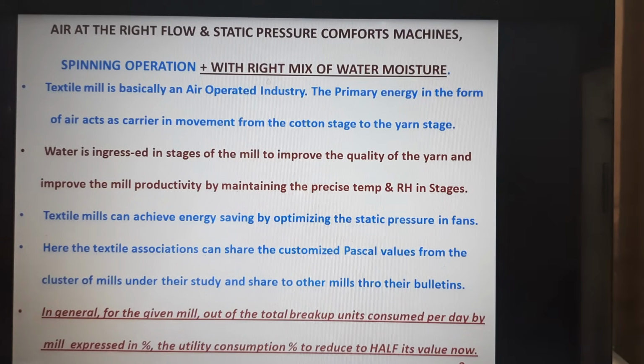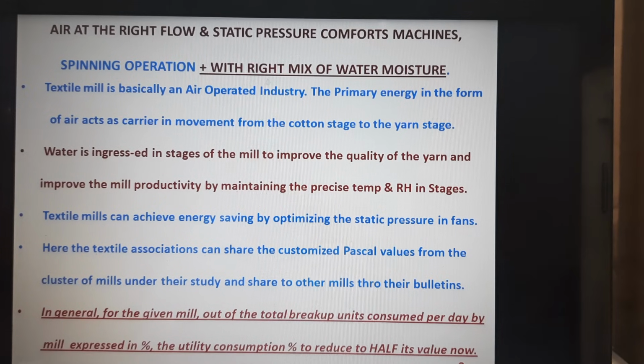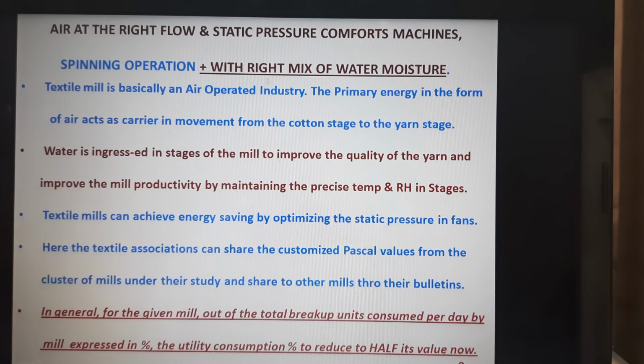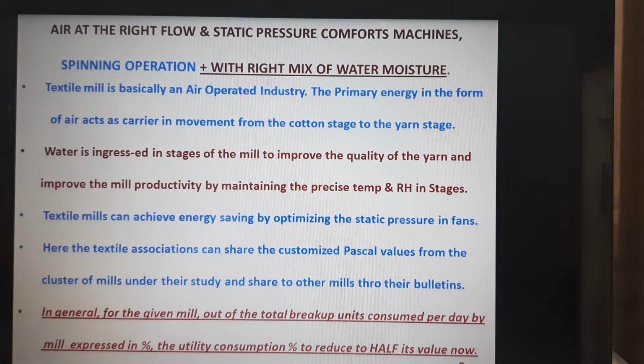In general, for any given mill, if you see the breakup of electricity consumption, let us say around 100% is the electricity consumption, and of the utility consumption, around say 10% is on the AC plant, which needs to come down by half. If the compressor consumption is around 6% or 8%, that needs to come down to 3%. Like that, all the utility percentages in the mill's electricity consumption have to come down by half of their level by improving their energy efficiency levels as such.